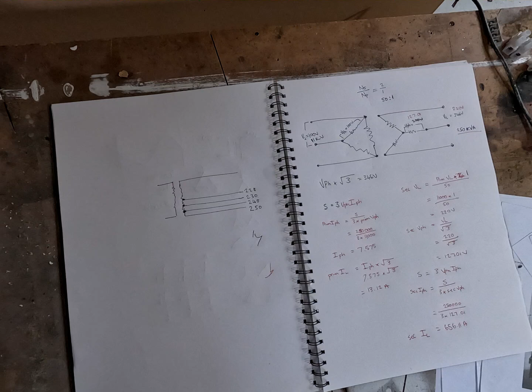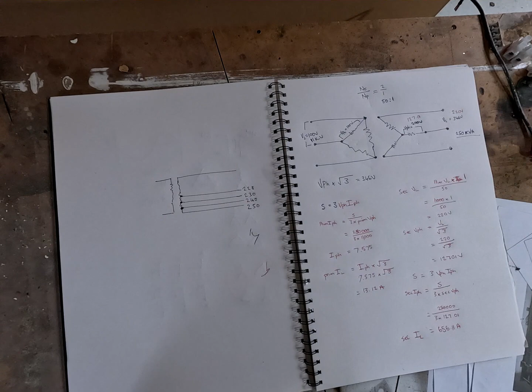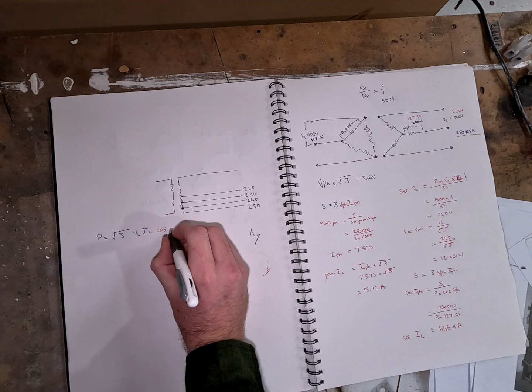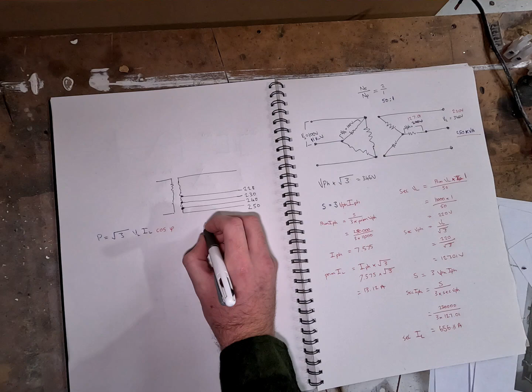There's a couple of calculations to know about the power triangle. I'll read this out because it explains it best. True power is the resistive power consumed by a balanced three-phase load. It's also called active power, measured in watts, kilowatts, or megawatts. The formula to find true power, P, is the square root of 3 times the line voltage times the line current times cosine of the power factor angle.